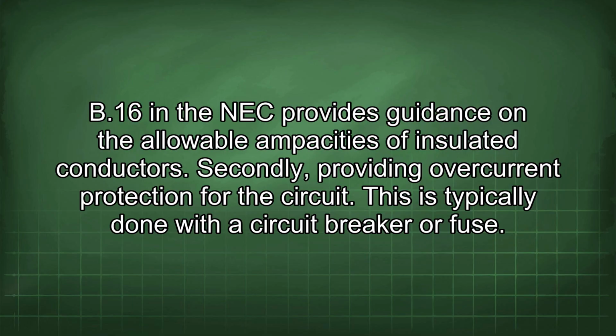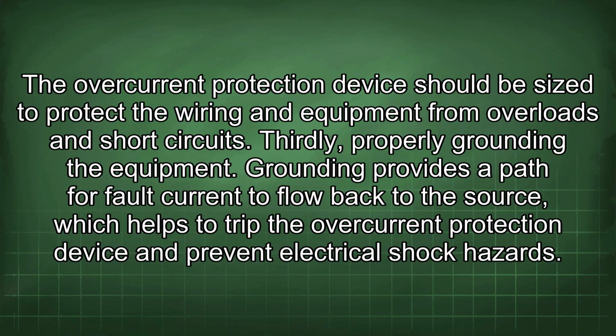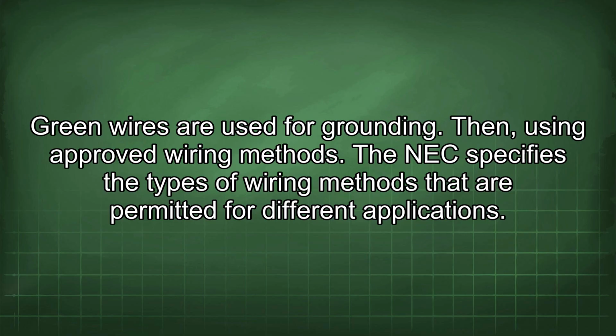Secondly, providing overcurrent protection for the circuit. This is typically done with a circuit breaker or fuse. The overcurrent protection device should be sized to protect the wiring and equipment from overloads and short circuits. Thirdly, properly grounding the equipment. Grounding provides a path for fault current to flow back to the source, which helps to trip the overcurrent protection device and prevent electrical shock hazards. Green wires are used for grounding.